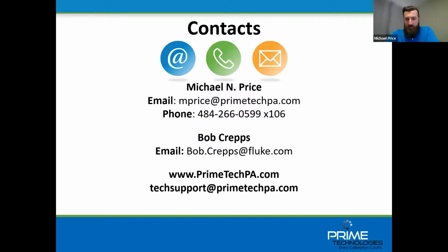All right, we have another question from China, a follow-up on the 753. Would the 753 be able to perform the trim like you showed with the 754? Would we have the full capability to download calibration from ProCal to the 753, performing the calibration as you demonstrated? Absolutely, yeah. So what you would do is you would just do your as found and your as left from the calibrator itself. You wouldn't do the adjustment from the 753.